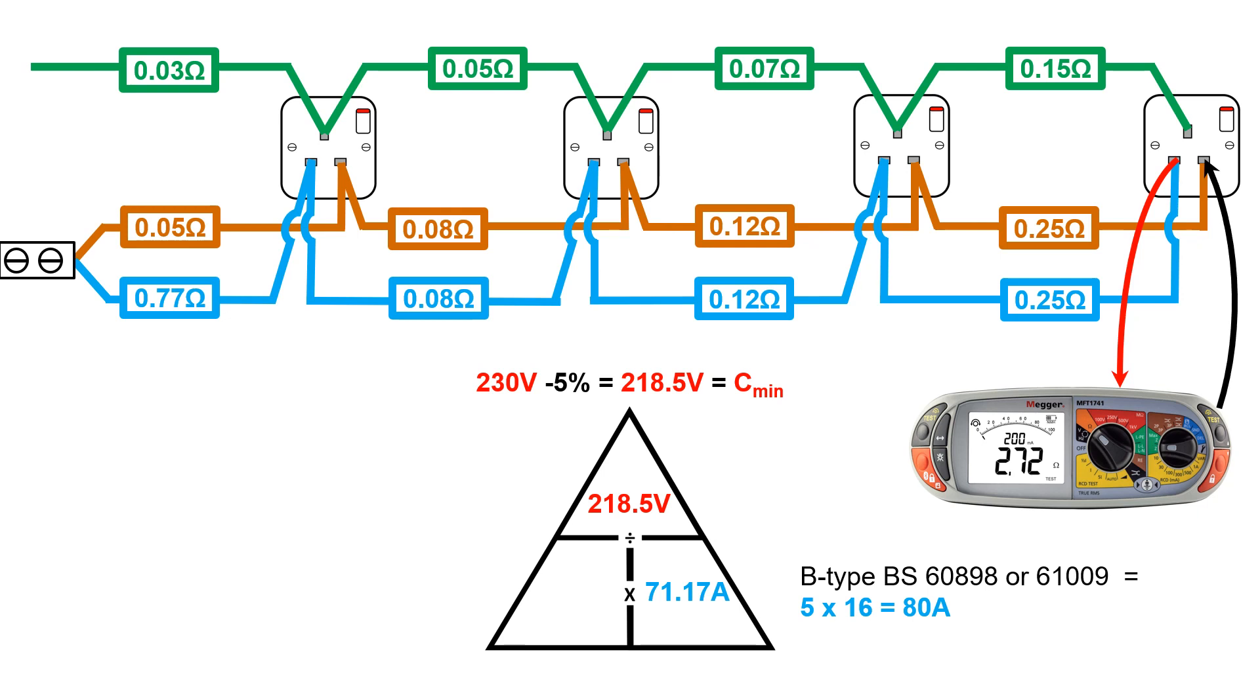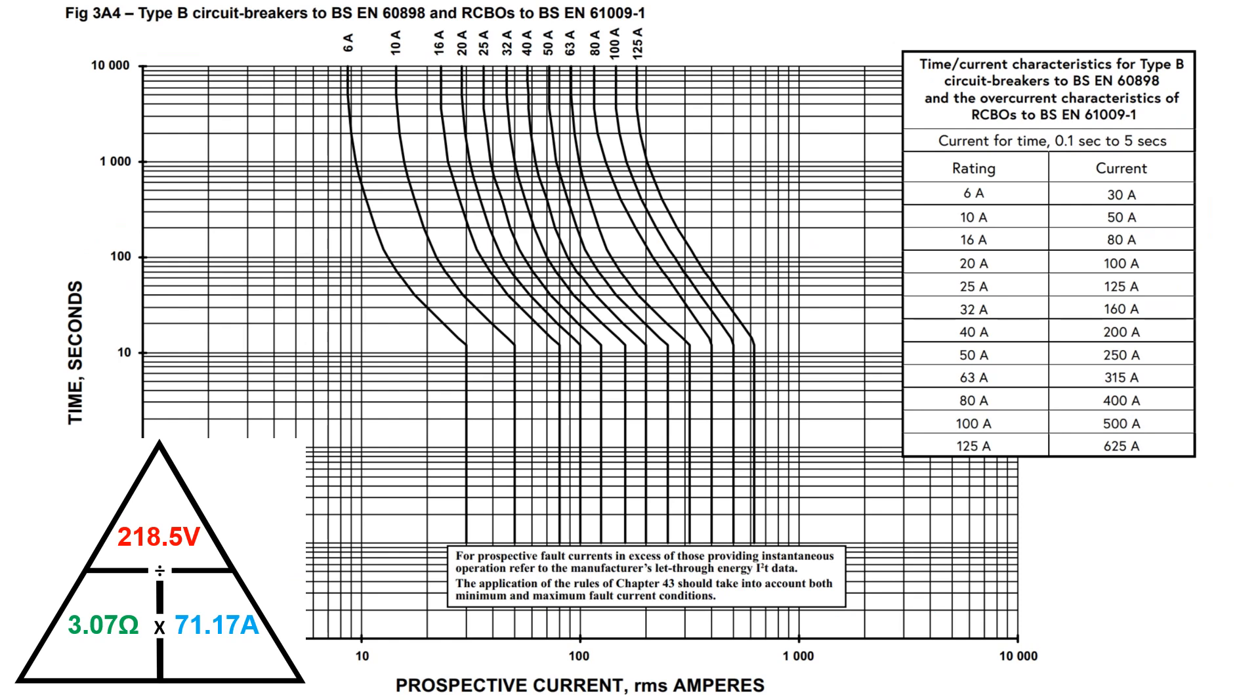However, the untested neutral has a higher resistance, which doesn't meet that value. Once the ZE of 0.35 is added onto the 2.72 ohms measured by the MFT, we get a total circuit resistance of 3.07 ohms, which far exceeds the maximum 2.73 ohms required to operate the circuit-protected device in the required time. This is because the maximum current that can flow is only 71.17 amps and we needed a current total of 80 amps.